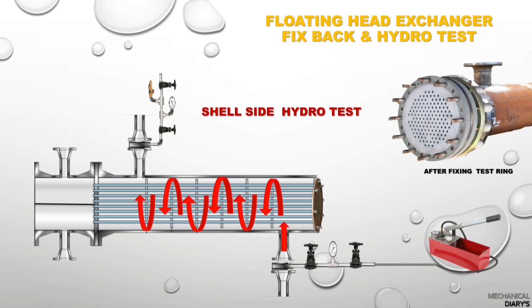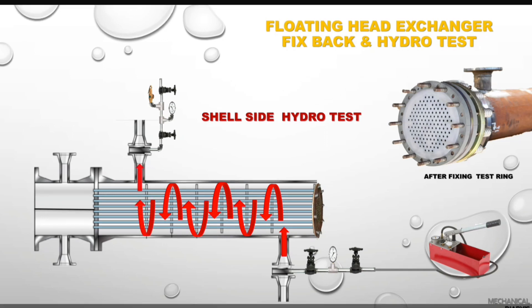While fixing the test ring, use Teflon gland packing — do not use graphite, as graphite may cause leakage during the hydrotest. Once the test ring is fixed, you can start pressurizing the shell side from the shell side bottom nozzle.